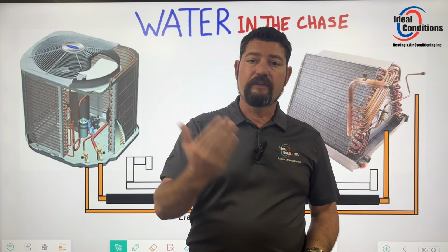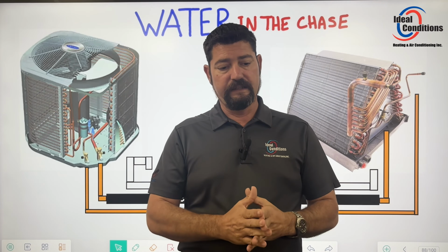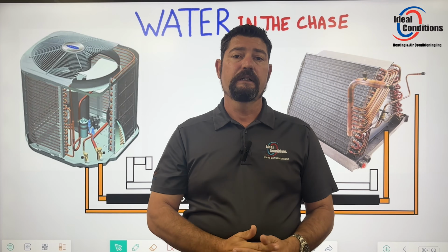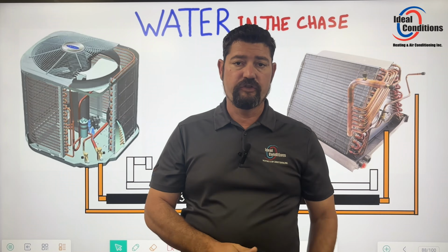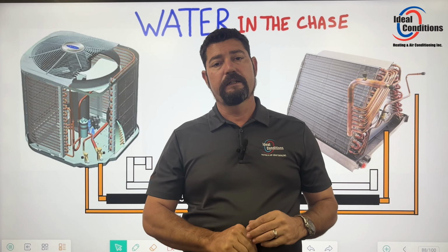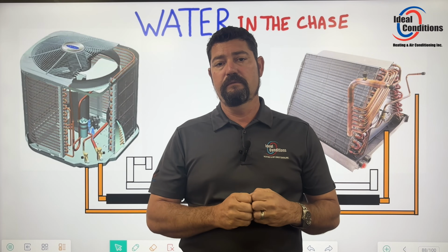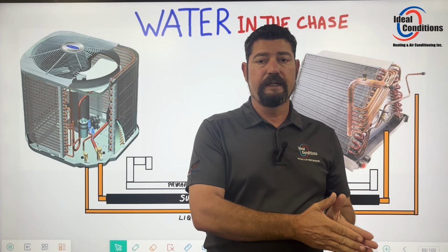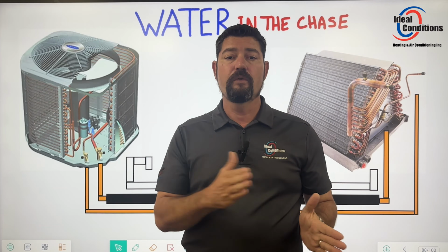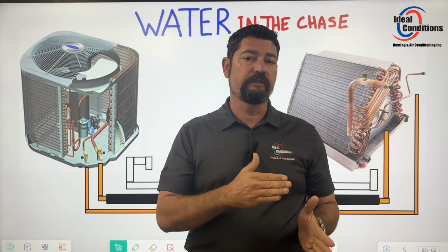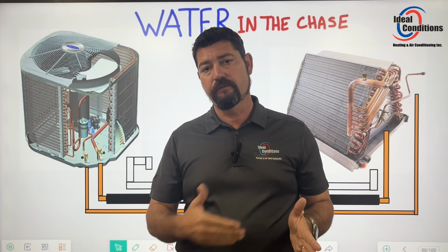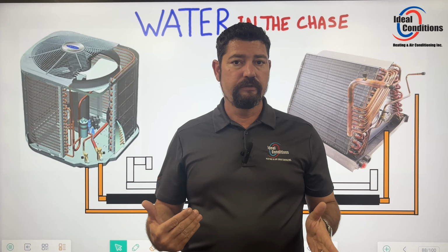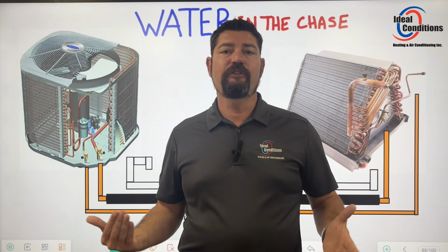Now you have heat index directly affecting the temperature of that copper as it journeys down that structure, that building. So you're losing the temperature that you had at your evaporator coil, and you're gaining much more. So it's not bad in the sense of liquid returning to the compressor, like water in a chase will do. Instead, you're going to read a high superheat.